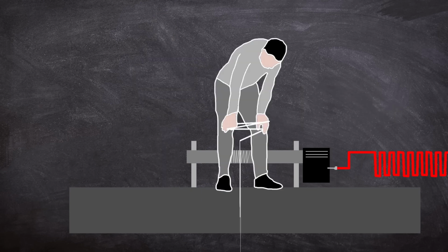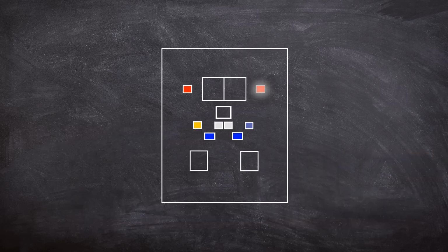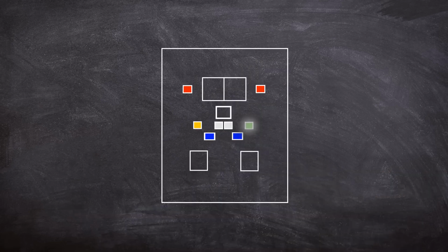The alarm continued, and in order to trick the system, the operator pulled on the cable until it left the hoist mechanism. After this, he fed it back down, which activated the micro switch, telling the system the source was down. The operator returned to the control panel. He found that the red general failure light and source up light were still on. He went back to the roof and managed to manipulate the micro switch so that upon returning to the control panel, the green source light down was now on.